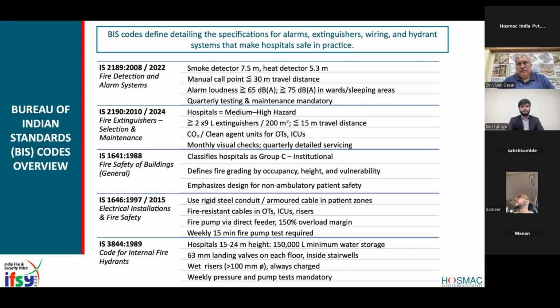So the idea is that if it is a dry riser and the fire is caught, it will take some time to reach the water up to that fire space. Because of that, it has to be always a wet riser and the system has to be always pressurized, so that when the fire is caught, immediately the water will come out and sprinkle and extinguish the fire.